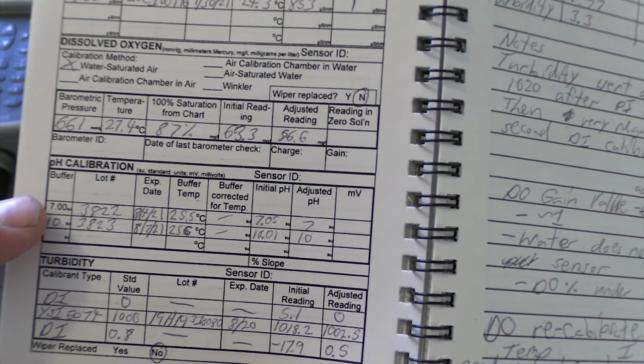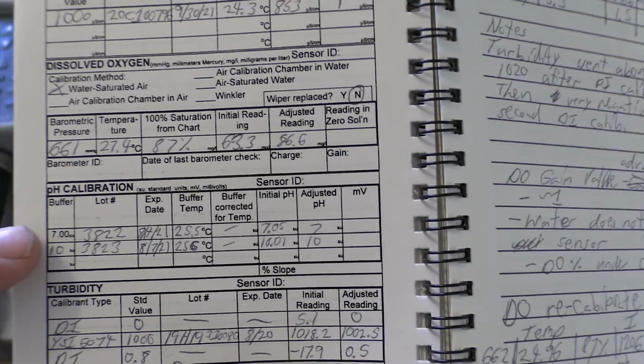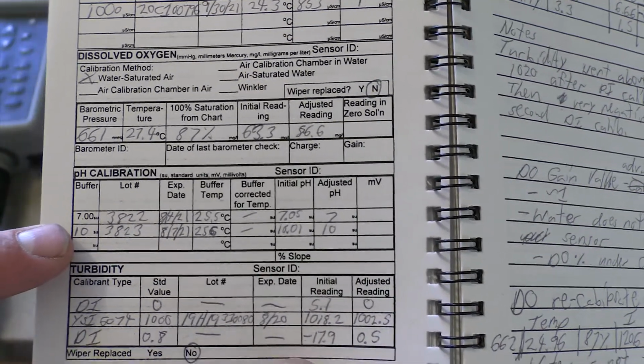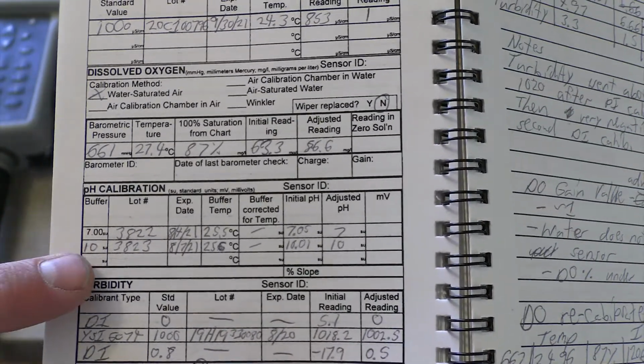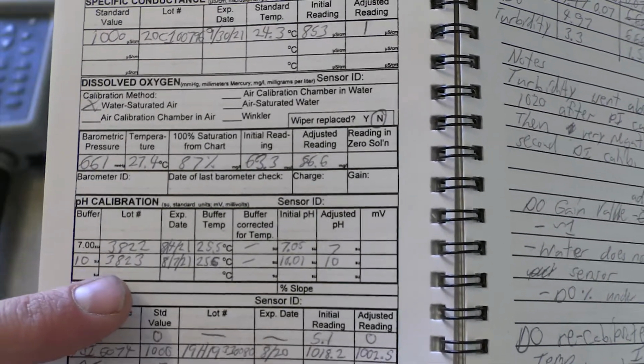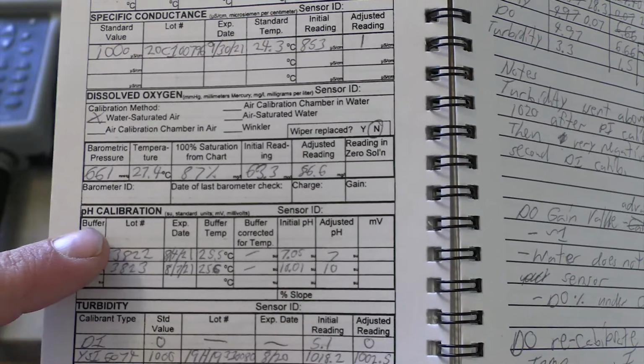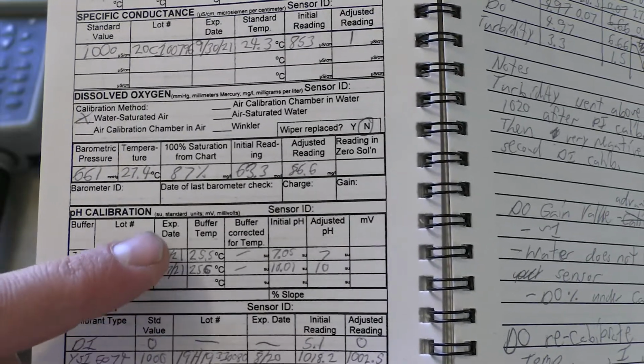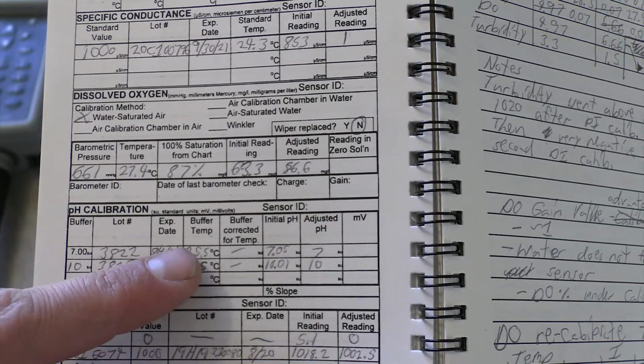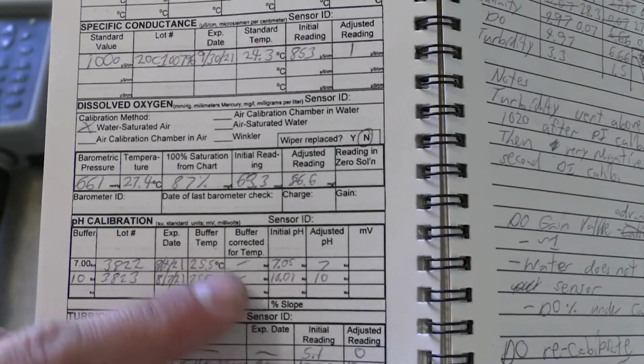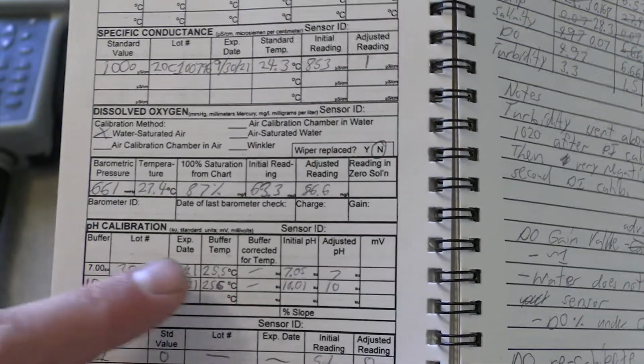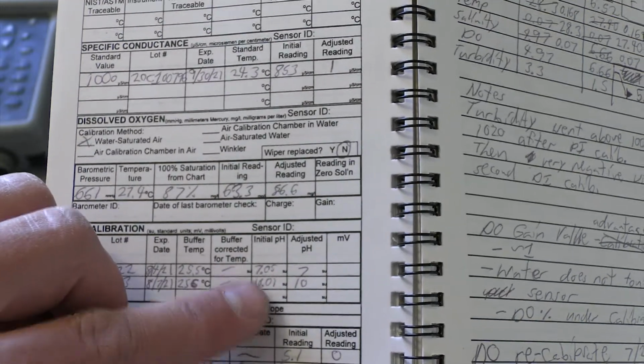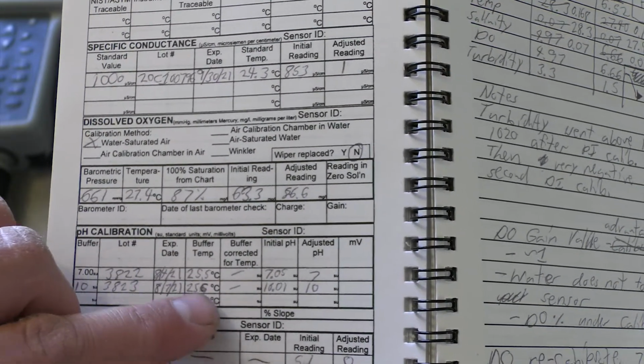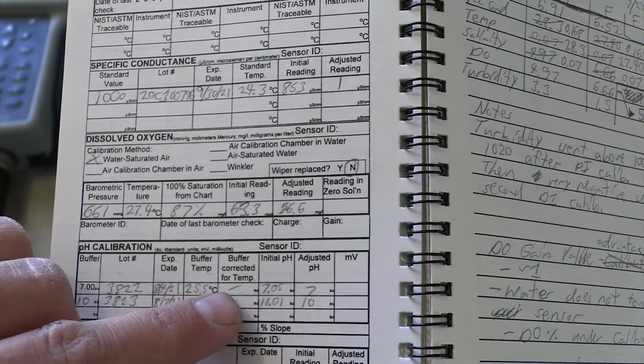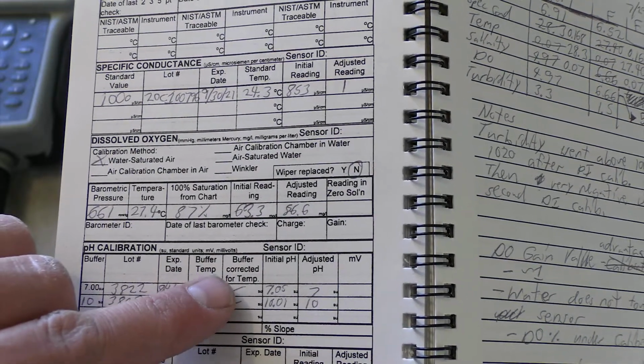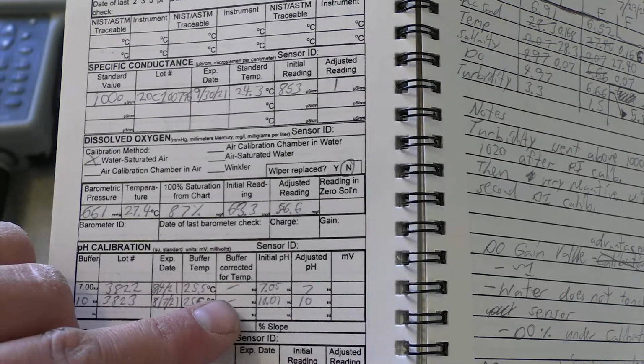And so for pH calibration, we use two solutions, a 7 and a 10. We can start off with a 7 and then finish with a 10, so we have a 2-point calibration just to make sure it's in point. And then we put in the lot number, which is on each bottle, the expiration date for each buffer, and the initial buffer temperature. That's where it's important to get that initial temperature, because it will actually change the initial pH. So if the temperature is, say, 16 degrees Celsius, then there is a buffer corrected value, which is on the side of the bottle.